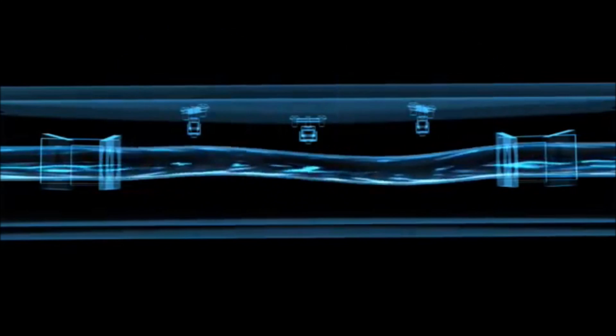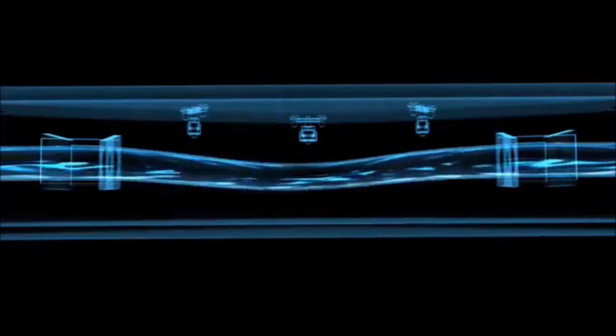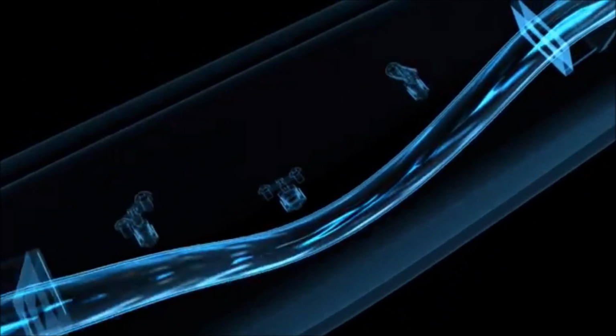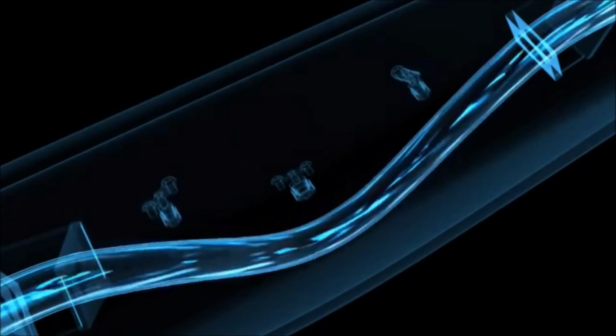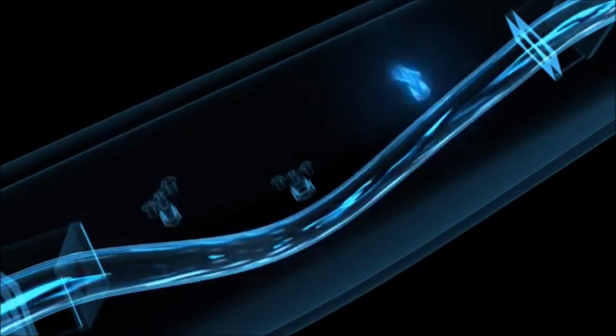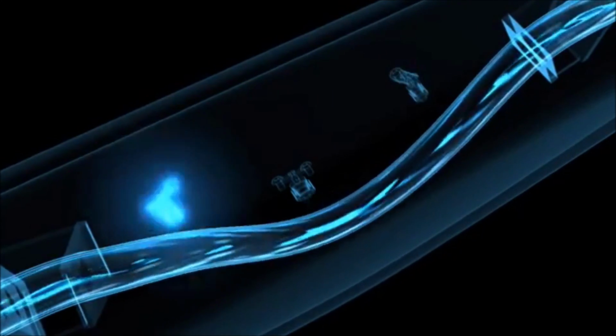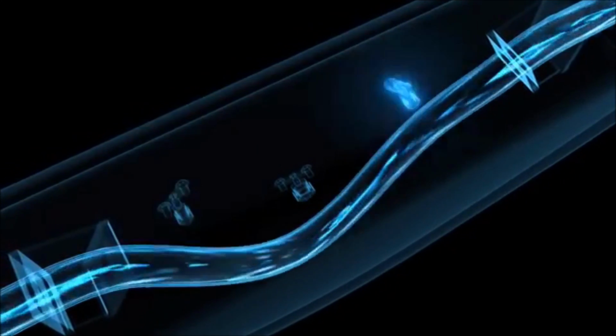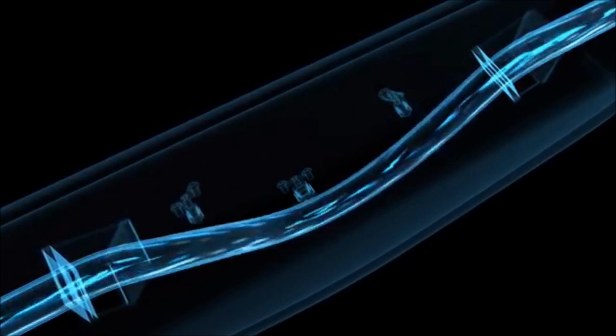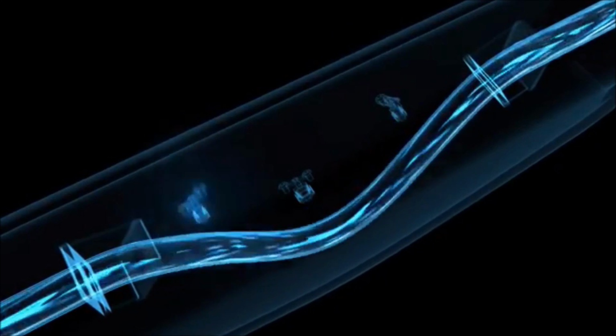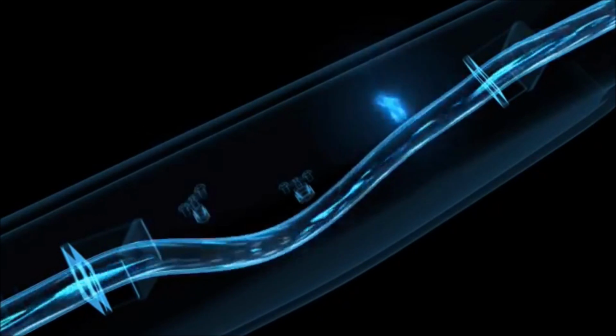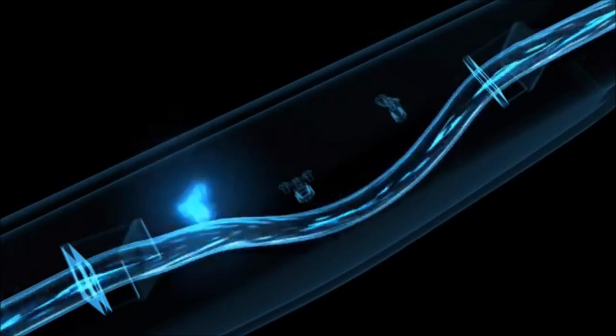Now, due to the Coriolis effect, the inlet and outlet sections of the tube oscillate in different directions at the same time. The highly sensitive sensors pick up this change in the tube oscillation in terms of time and space. This is known as the phase shift, and is a direct measure of how much liquid or gas is currently flowing through the pipe. The higher the flow velocity, and thus the total flow, the greater the deflection of the oscillating measuring tube.